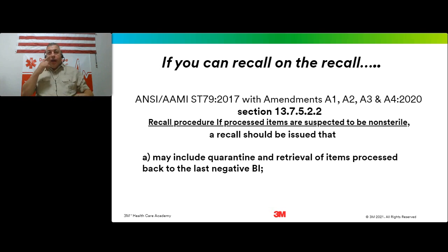So again, in that scenario where you test weekly, hopefully those cycles - I've seen people do a number of things. I've seen people put policies into place sometimes that if they're not running implants, some people will test daily, but then they'll also run a noon test and an evening test. That's certainly breaking down the amount of goods also, but there's an even better way to get there.